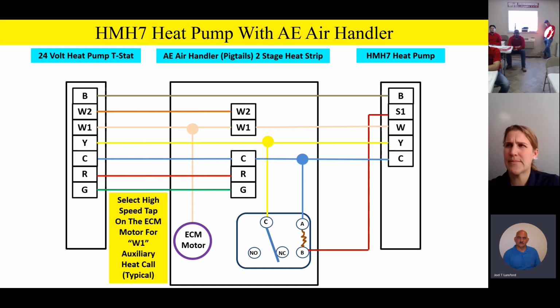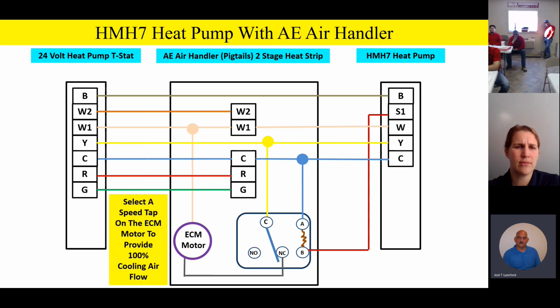So the high speed tap typically is going to go to your auxiliary heat input. That way it'll drive that motor to high speed anytime you have an auxiliary heater. If the unit goes into defrost, remember, we're going to bring the heat strips on during defrost on a heat pump as well. On the normally closed contact of that relay, you're going to go over to that ECM motor and select the speed tap to give you 100% cooling airflow. So with the unit just coming on right now with the relay de-energized, we're going to drive it to high speed airflow. However, on the normally open contact of that relay, we're going to go over and select a speed tap for about 60 to 65% airflow.